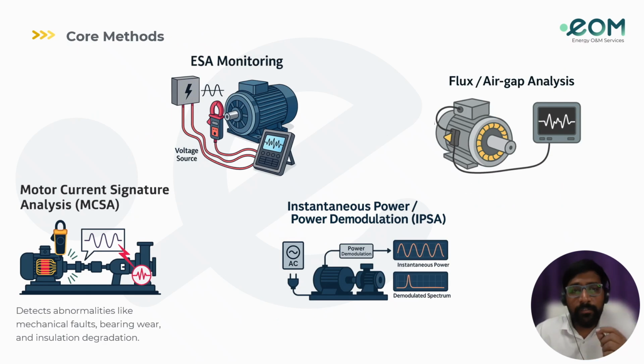And we'll see the core methods. The first thing is motor current signature analysis, MCSA. Motor current signature analysis is a predictive maintenance method used to evaluate the condition of electric motors. It can identify anomalies including mechanical problems, bearing wear, and insulation deterioration by examining the electrical current waveforms, enabling early identification of possible problems and prompt maintenance action. This non-intrusive technique helps us avoid unplanned downtime and expensive repairs as well.